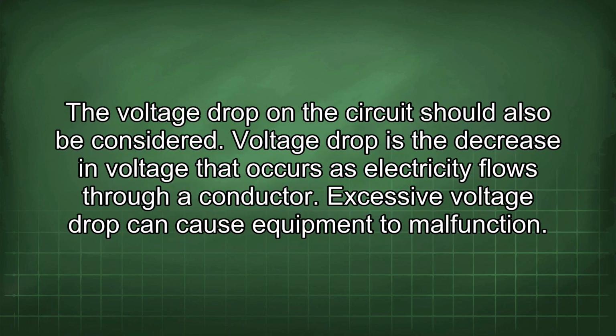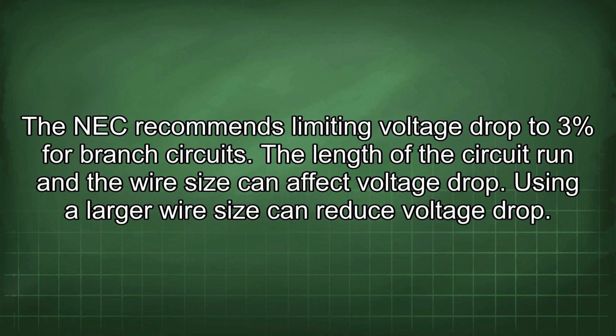The voltage drop on the circuit should also be considered. Voltage drop is the decrease in voltage that occurs as electricity flows through a conductor. Excessive voltage drop can cause equipment to malfunction. The NEC recommends limiting voltage drop to 3% for branch circuits. The length of the circuit run and the wire size can affect voltage drop. Using a larger wire size can reduce voltage drop.